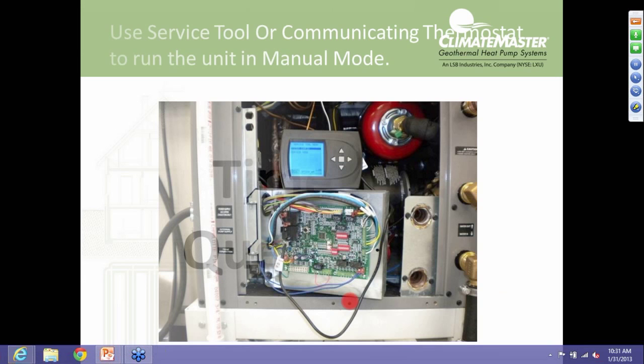Okay, we're going to skip over that. We're going to continue on here with a few other things before we take some questions. I want to cover here in the next several slides, again, how we commission these heat pumps, because I think it's very, very important. And again, we're going to do this with a service tool or the thermostat. Again, I'm a big fan of the service tool because you can do it right in front of the heat pump as this picture shows here. We've got our wire whip, we plug right in, we can control this right in front of the heat pump. We're not going in and out of wherever the thermostat's located from the unit.